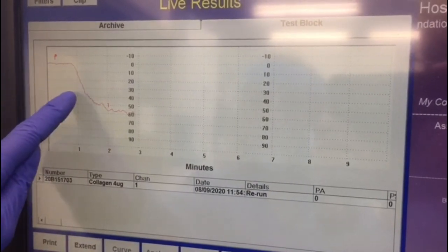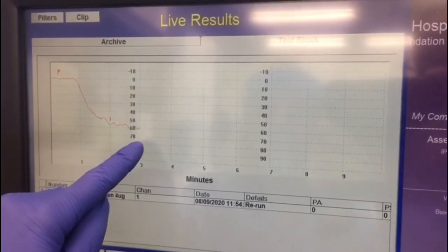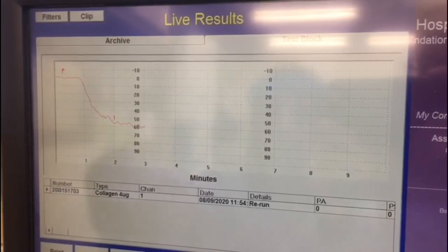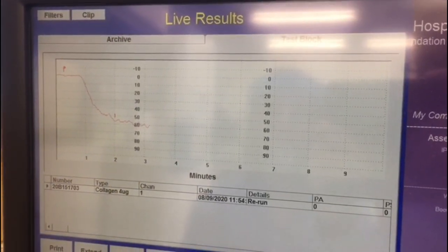We want to see a nice curve forming. This is the point where I've added the reagent, and you can see as the curve forms, this indicates that the platelets are clumping together and the light transmission is increasing. If the patient sample didn't form a curve and ran straight across, this could indicate that the patient has a platelet defect.